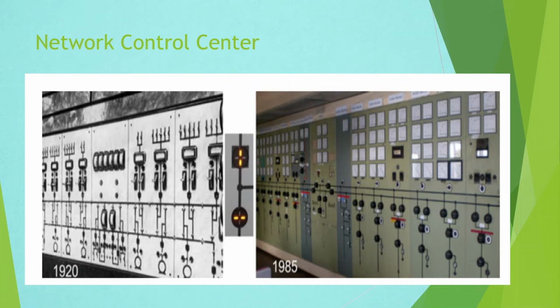The substation control level provides a communication interface to the network control center, and if requested to further network service providers like asset and maintenance management, network planning or protection supervision. Not all available data is communicated between all of the levels. Instead, the information exchange has to be engineered.